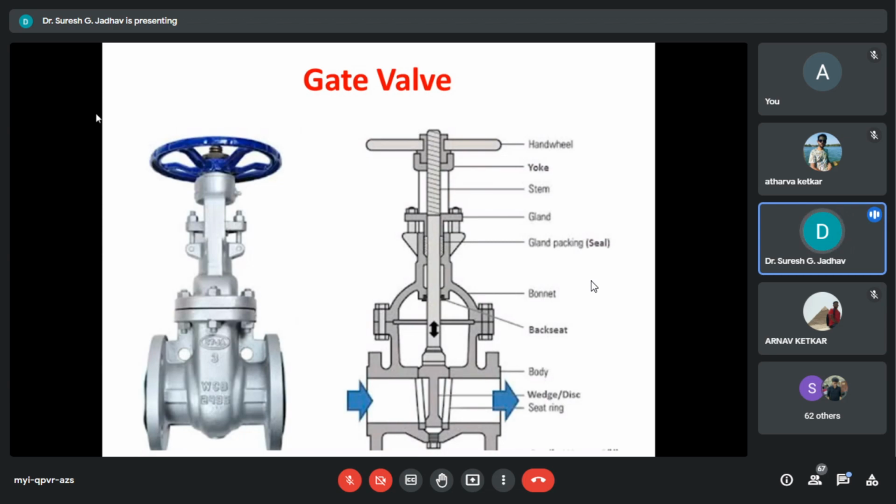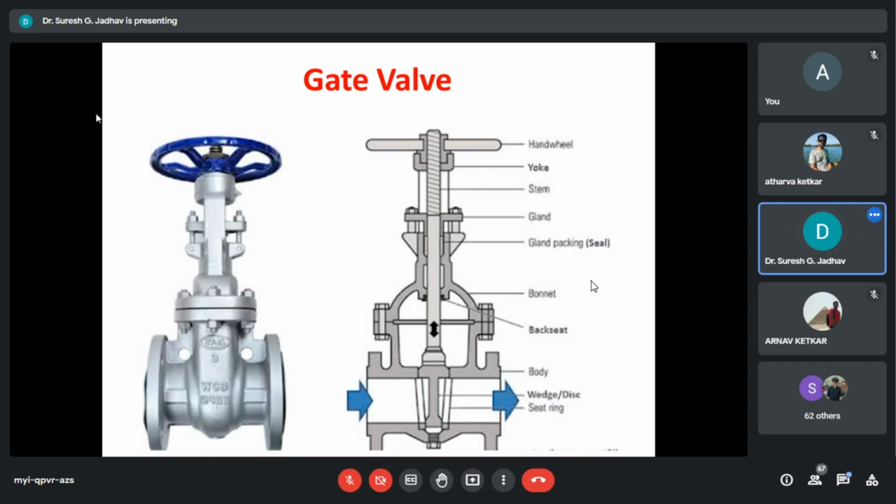The regulatory code specifies that the stuffing box should accommodate minimum 6 packing rings for class 150 hash. As regards higher rating valves, it should have lantern rings with 5 packing rings above and 2 packing rings below the lantern. Lantern is not provided for class 150 hash.